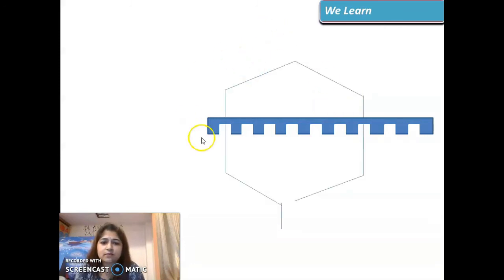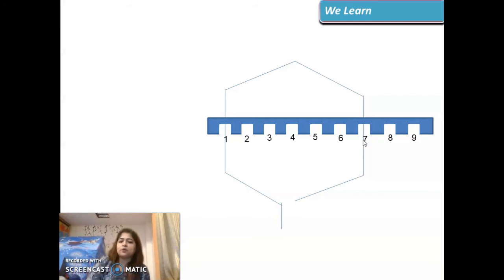Suppose this is the coil, so placed that if one coil side is in the first slot, in front of one pole, then the other coil side is placed six slots after, because as we have seen in the last slide, 24 by 4, there are six slots for each pole. That is why when we say one pole pitch, it is six slots.